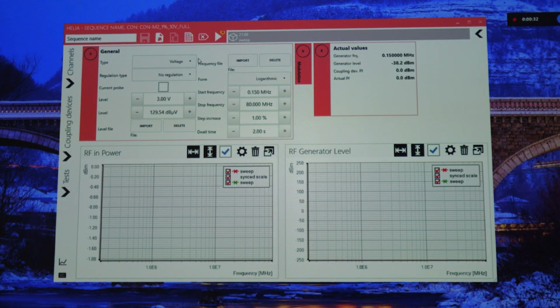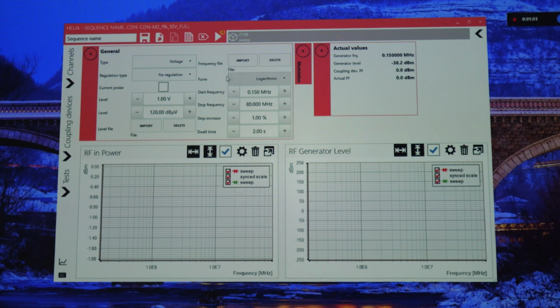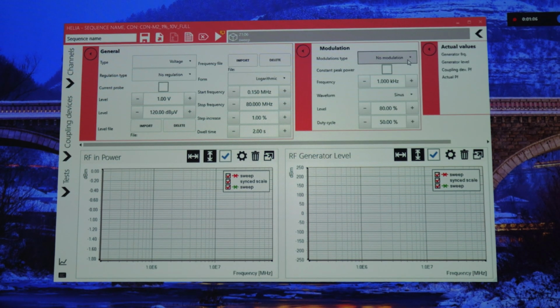Once this opens up, it gives me a whole set of other screens, so I can change whether it's a voltage or magnetic field, my start and stop frequencies, the step size, the dwell time, and my test level. For my example today, I'm going to leave it at 1 volt. I'm not going to use a current probe, but you can also technically use a current probe to measure downstream to make sure you are getting the signal onto the device under test. You could also set the modulations: internal AM, external AM, pulse modulation, whether it's a sine, triangle, or rectangular waveform, the frequency of the modulation, the level of the modulation, and the duty cycle.